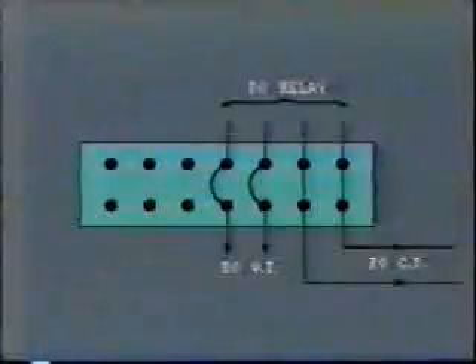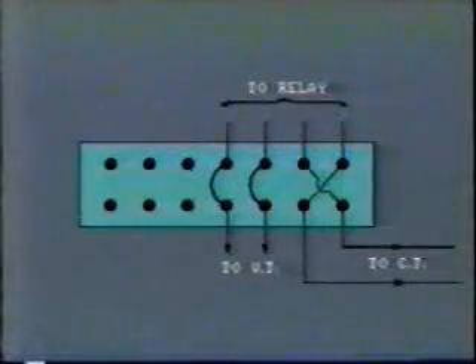This will act as a permissive to the overcurrent or other protective element, so tripping should not occur under normal operating conditions. To check the blocking element of the directional relay, we can simply reverse the flow of current to the relay by cross-connecting the CT connections at the test plug. In this situation, the directional element contacts should open.